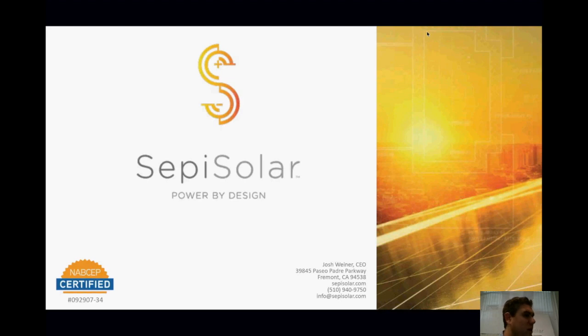So in broader categories: O&M happens at the thermal management level, at the software level with controllers, communications, and controls — those all need to be working and updated. If you're on the customer side of the meter, demand tariff rates change, so making sure you're always optimizing your system for the rate you're on, or the rate you should be on, could be regular maintenance, as well as augmentation strategies, system inspections, checking for leaks and pumps. How's that, AJ?